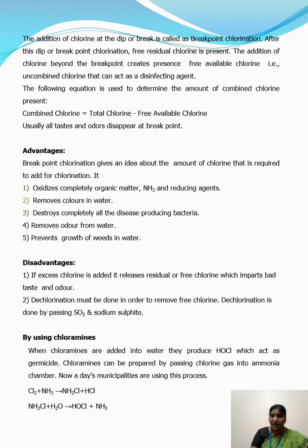So this particular point is called the breakpoint chlorination. After this dip, you will have the free residual chlorine that is being released. The addition of chlorine beyond the breakpoint will create free chlorine only. So this is called the uncombined chlorine that will act as the disinfecting agent.